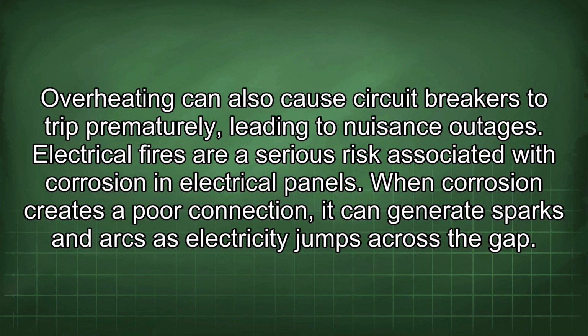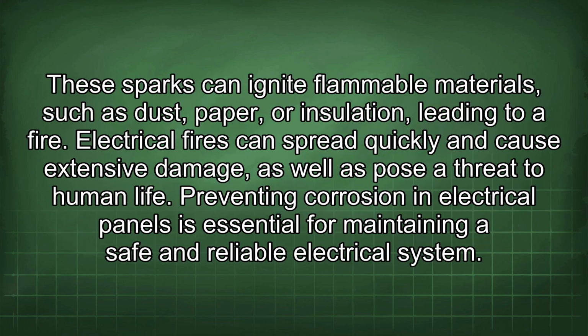Electrical fires are a serious risk associated with corrosion in electrical panels. When corrosion creates a poor connection, it can generate sparks and arcs as electricity jumps across the gap. These sparks can ignite flammable materials such as dust, paper, or insulation, leading to a fire. Electrical fires can spread quickly and cause extensive damage, as well as pose a threat to human life.